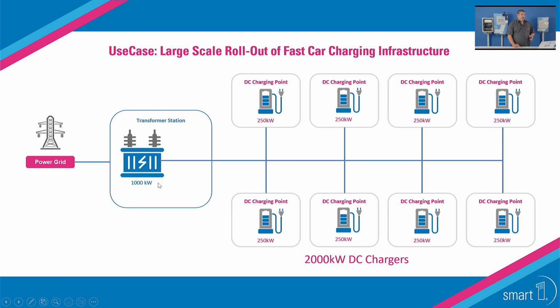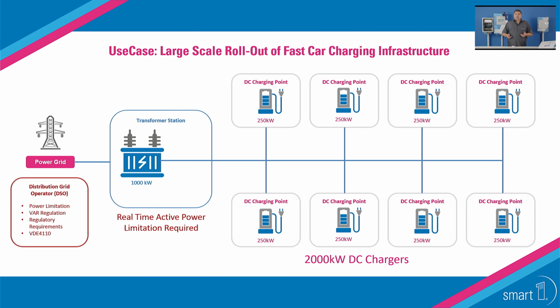In this case, we have a 1 megawatt transformer, and we have about 2 megawatts of DC chargers connected to this transformer. That leaves us with the requirement to have real-time active power regulation limitation, meaning we need to limit the charging stations in a way that we never overload the transformer station.